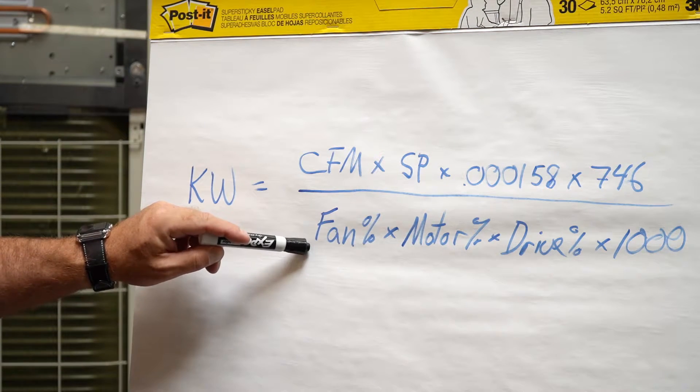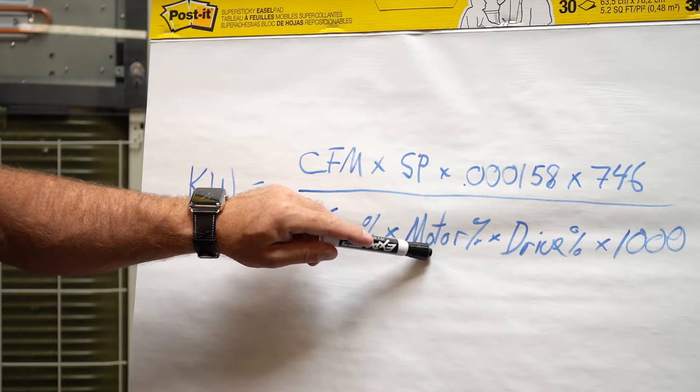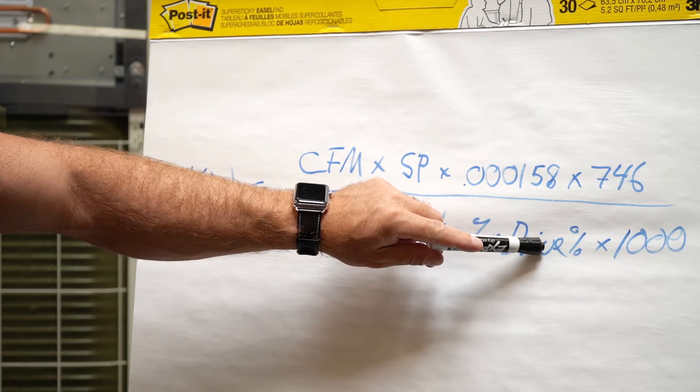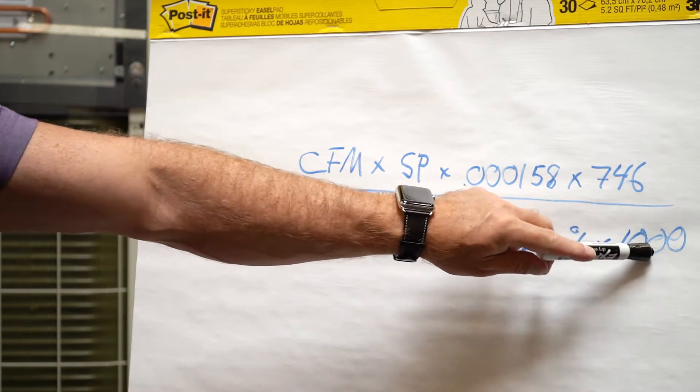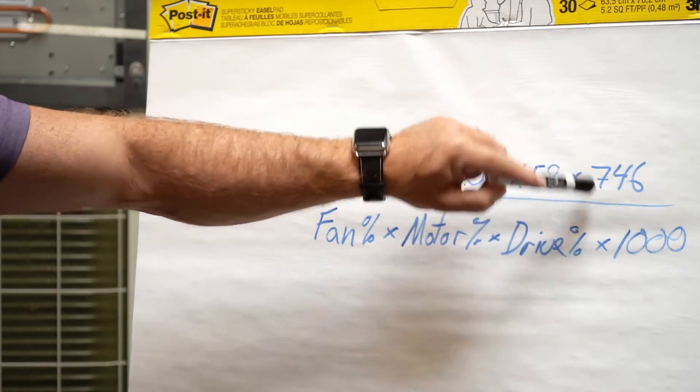In the denominator we have our fan efficiency multiplied by our motor efficiency multiplied by our drive efficiency, so if we're using a VFD we have losses there, or a belt system, times 1,000, which is the other component of this KW conversion.